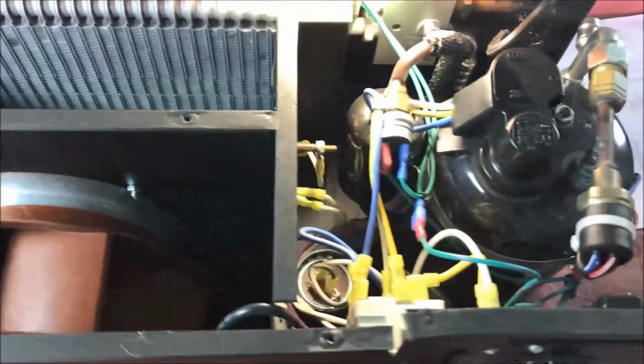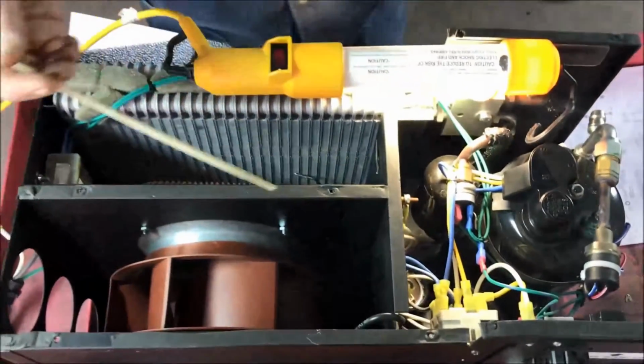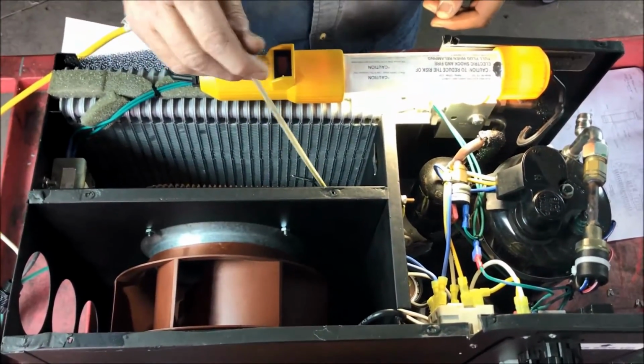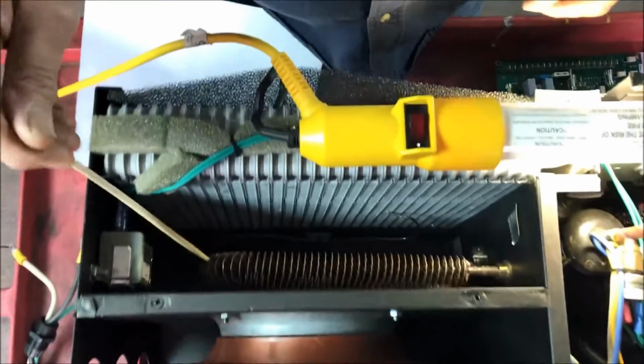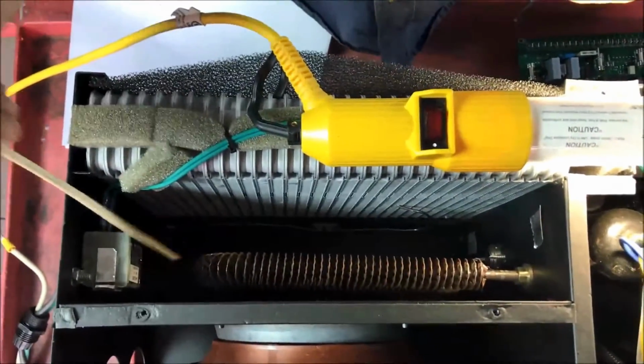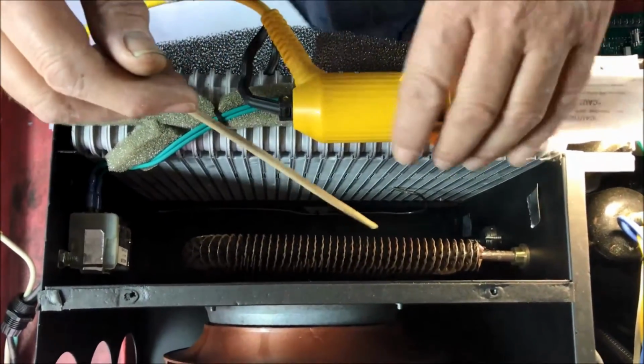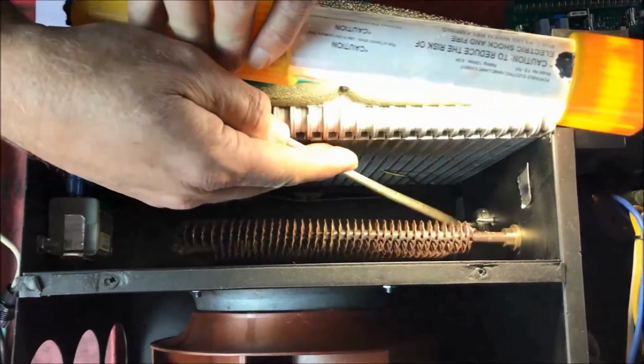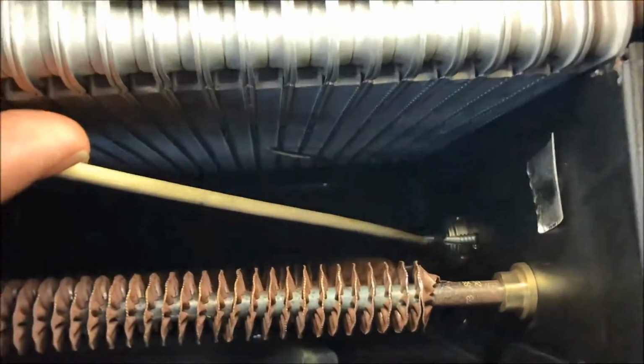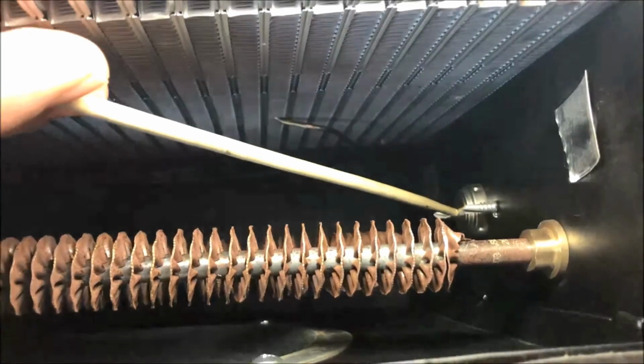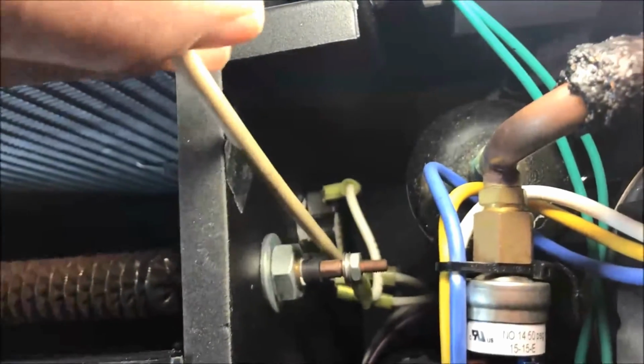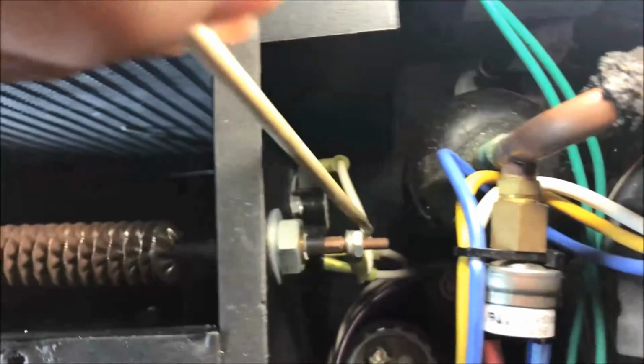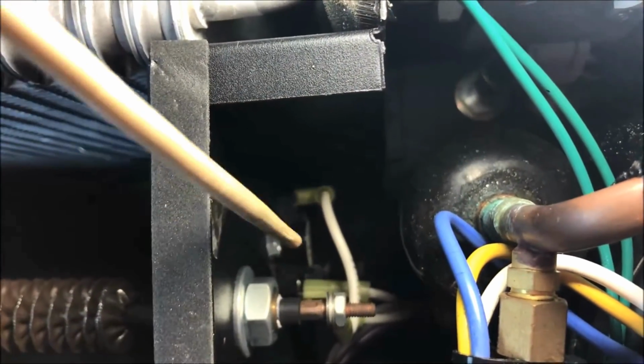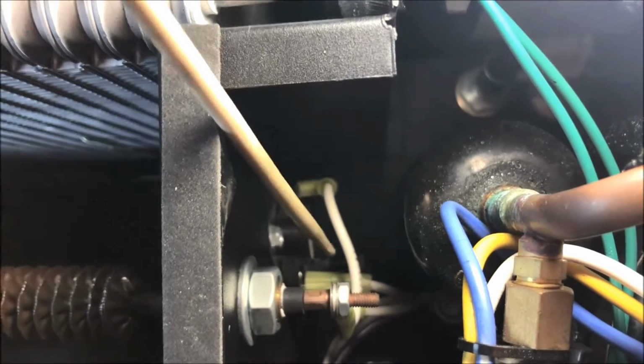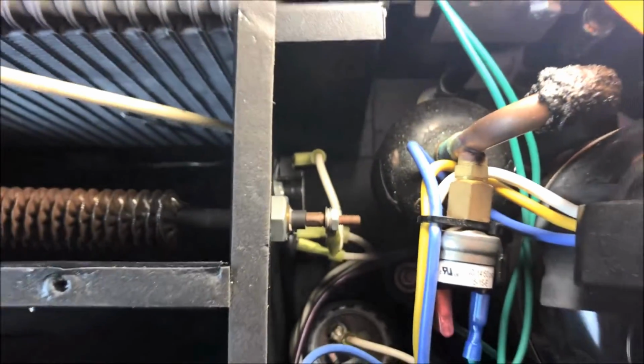Okay, we're going to talk about the heater. The heater is an electric element located in this section of the box. This section of the box is protected for temperature with this little device here, 170 degrees. If it senses that, it will open the white wired circuit and the elements will start cooling off. This is a Gen 2 unit.